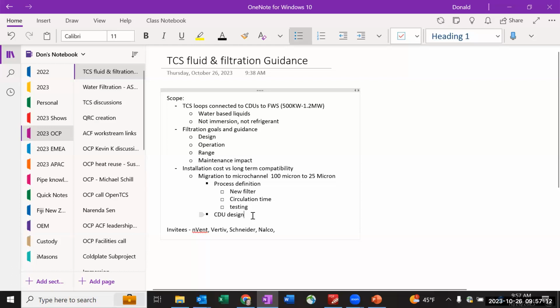The only thing I'd jump back to is CDU design, going from say a 100 micron filter down to a 25 micron filter. I'm going to guess you have a certain amount of head loss in the 25 micron filter, not just guess, sure, yeah, well that's what I mean.